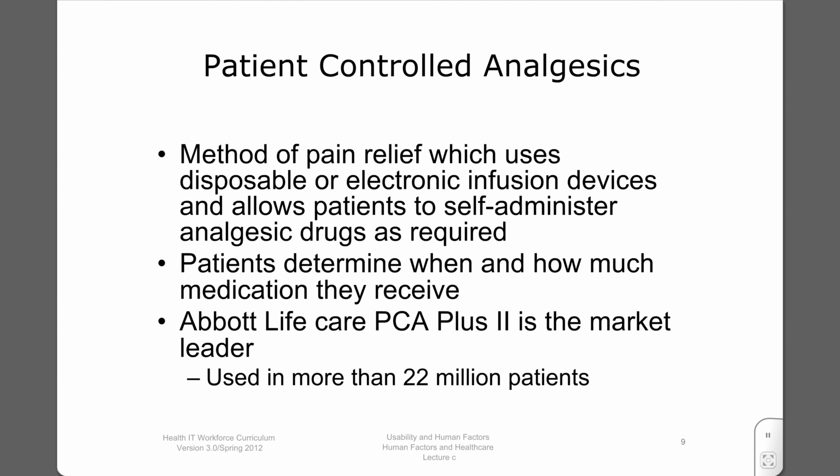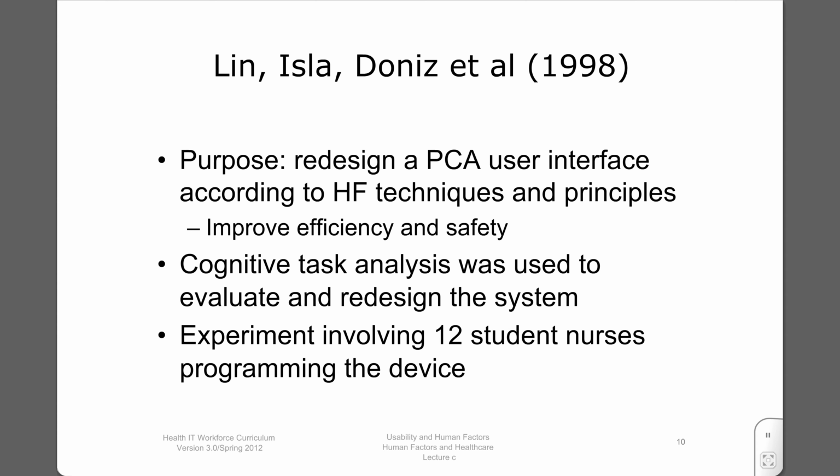Some of these devices are known to be inordinately complex, and some have poor records of patient safety. This has resulted in some of these less safe devices being pulled from the market. Lin and colleagues investigated the effects of 2 interfaces to a commonly used PCA device, including the original interface. Based on a cognitive task analysis, they redesigned the original interface so that it was more in line with sound human factors principles. Cognitive task analysis is a widely used method in human factors.